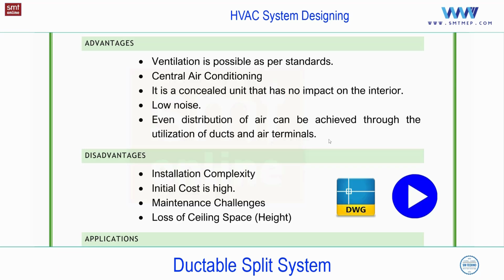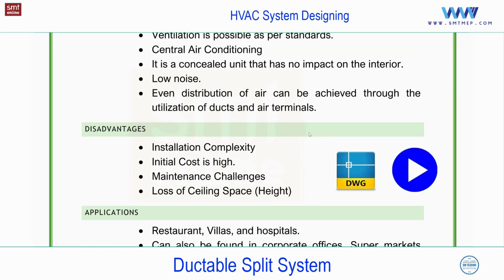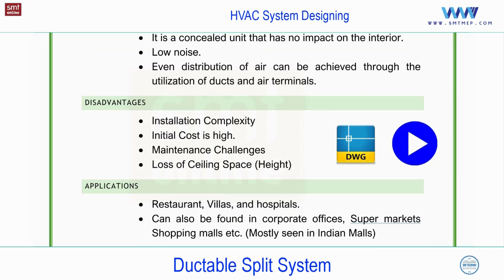Okay. Now, if you talk about disadvantages, you see installation complexity. Compared with what? Compared with the window and split. We require installation of duct, proper sizing of duct, and the air terminals, etc. Compared with the split, I'm saying, not with the others. Next, initial cost is high. Again, compared with the split system, because separate work is required, meaning ducting work is required. That also increases the cost of the project.